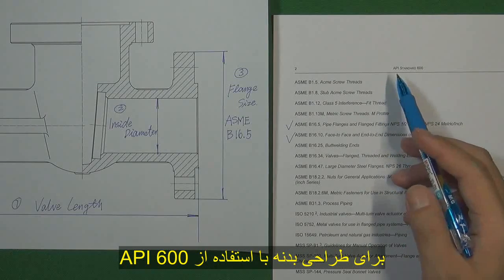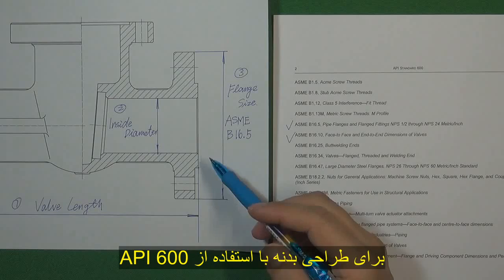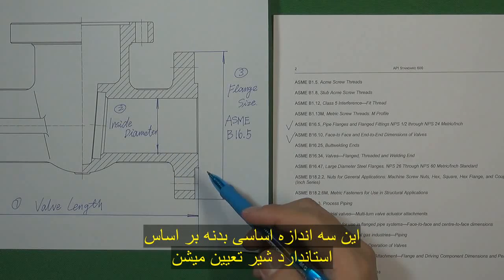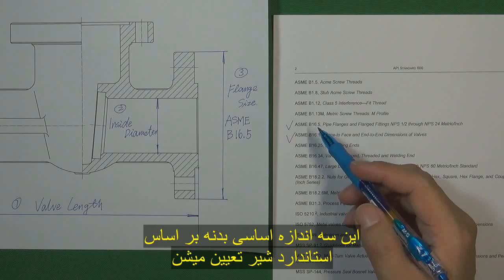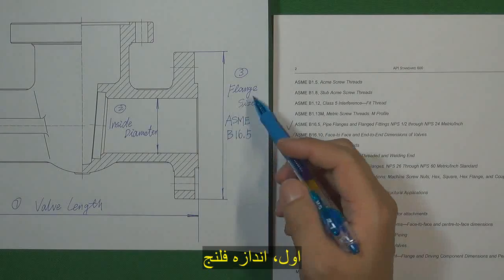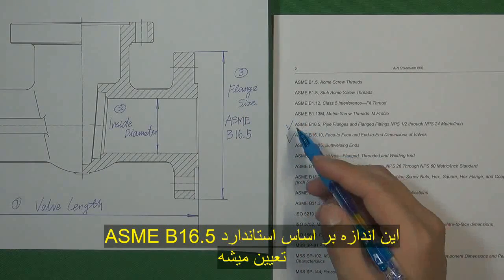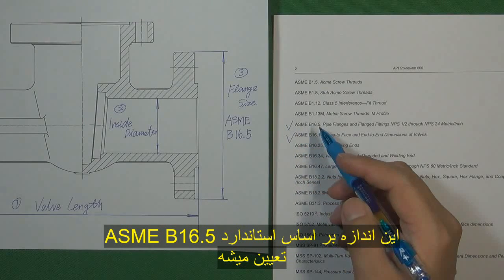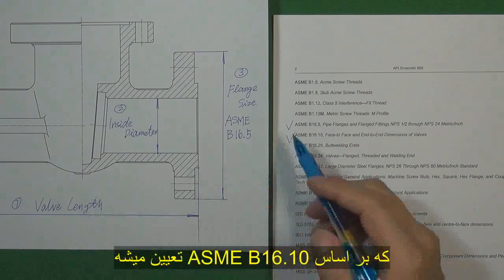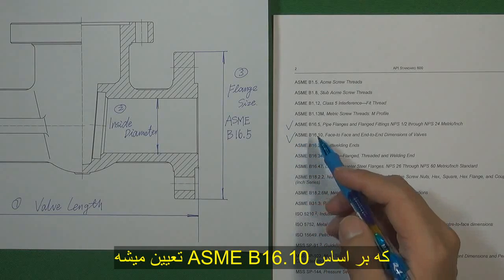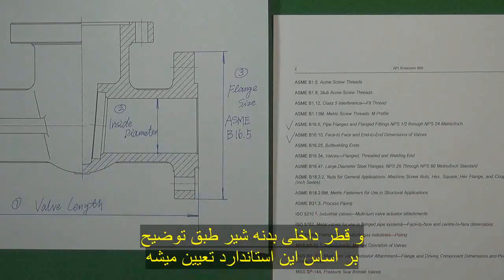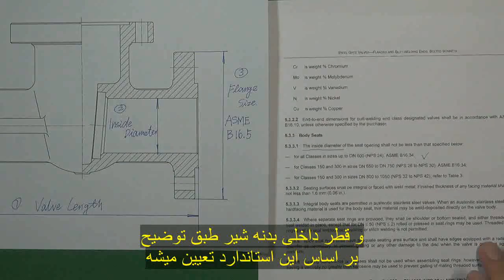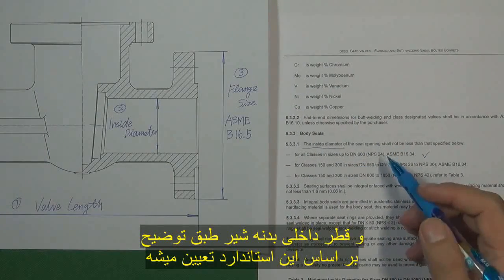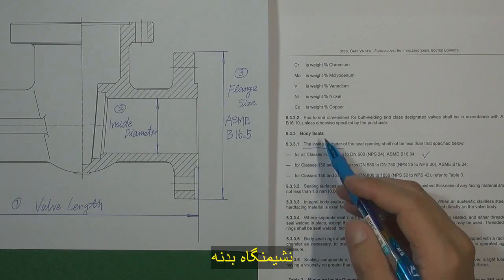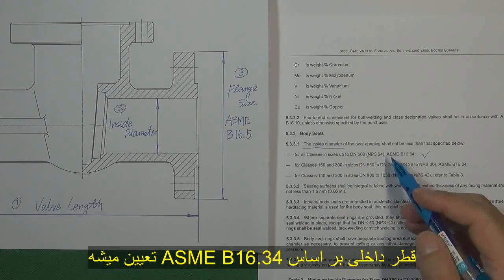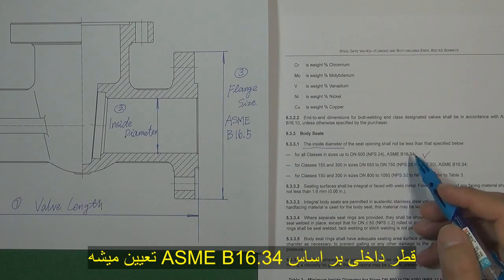When you're going to use API 600 to design a gate valve body, those three basic valve body sizes are determined by three valve standards. The first one is the flange size. Flange size is determined by the standard ASME B16.5. The next one, valve length. Valve length is determined by ASME B16.10. And the valve body inside diameter is determined by the standard according to the description, body seats. The inside diameter is determined by ASME B16.34.